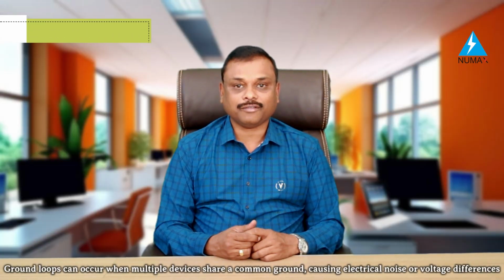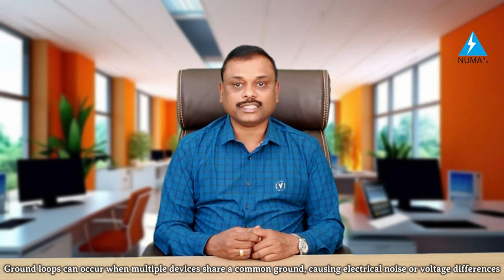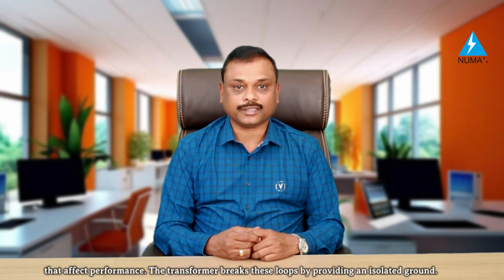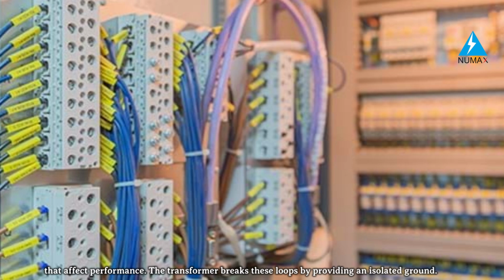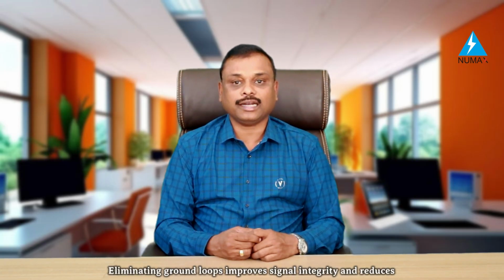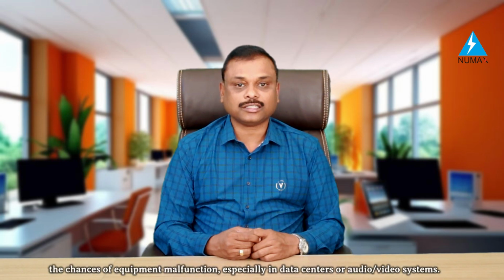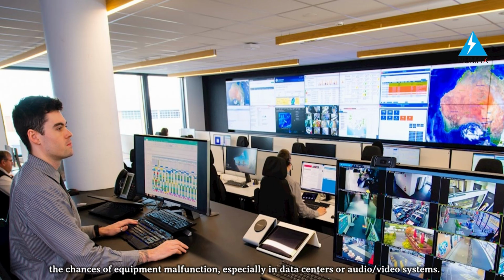Ground loops can occur when multiple devices share a common ground, causing electrical noise or voltage differences that affect performance. The transformer breaks these loops by providing an isolated ground. Benefits: eliminating ground loops improves signal integrity and reduces the chances of equipment malfunction, especially in data center or audio video systems. Number 4. Voltage stabilization and surge protection.